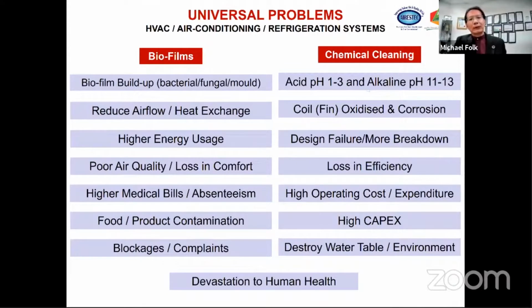When it comes to chemical cleaning, as I mentioned earlier, highly corrosive chemicals like acid, which is pH 1 to 3, or alkaline pH 11 to 13, will cause the coil fins to be oxidized and corroded. This leads to design failure, more breakdowns, loss in efficiency, higher operating costs and expenditures, and higher capital expenditure because you may have to replace the whole aircon system. It also destroys the water table and environment. Ultimately, it is unhealthy for everyone, including the humans in the building.